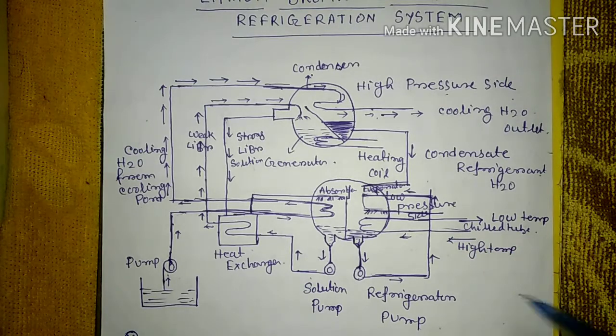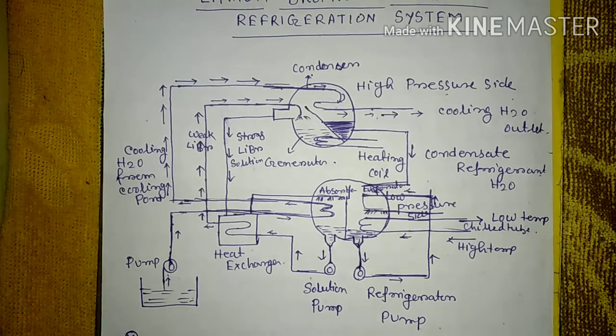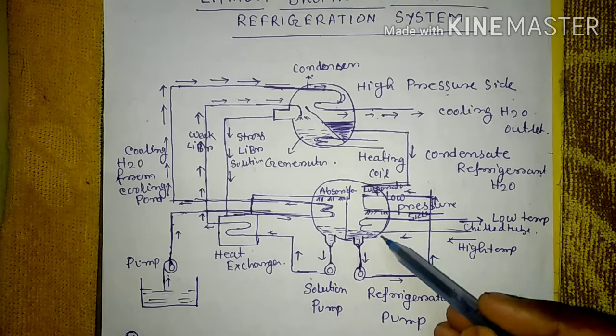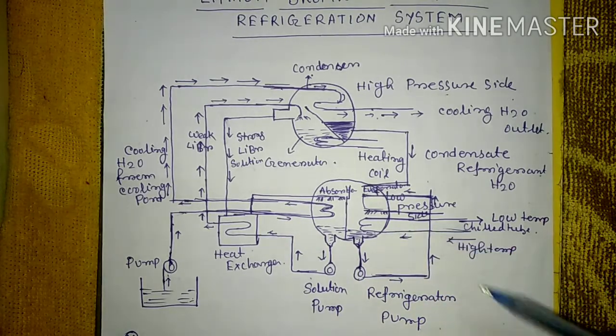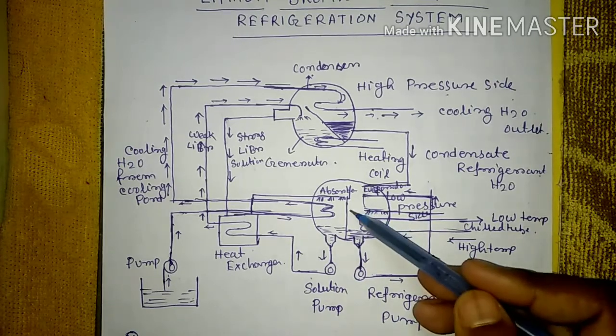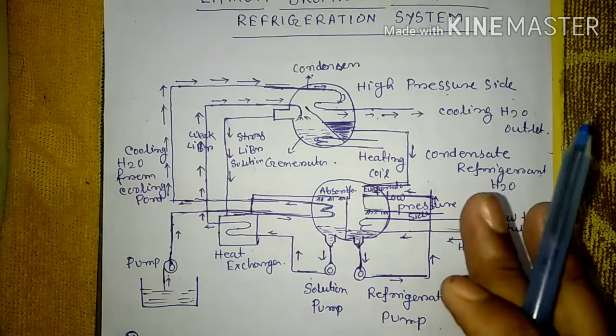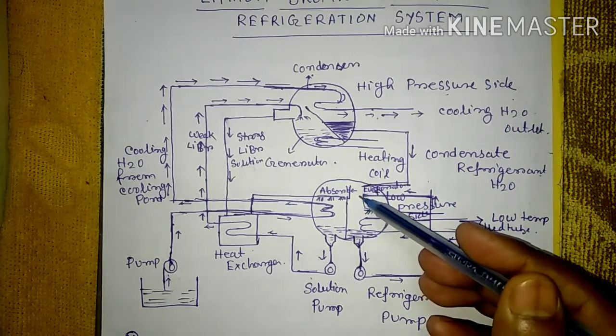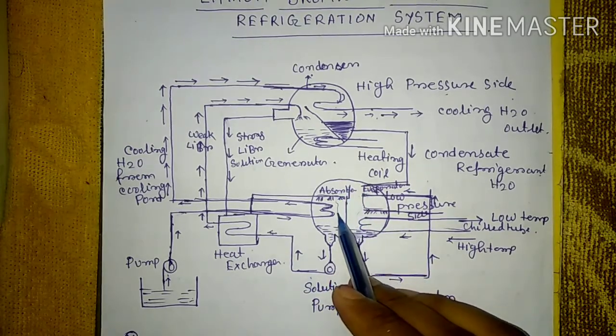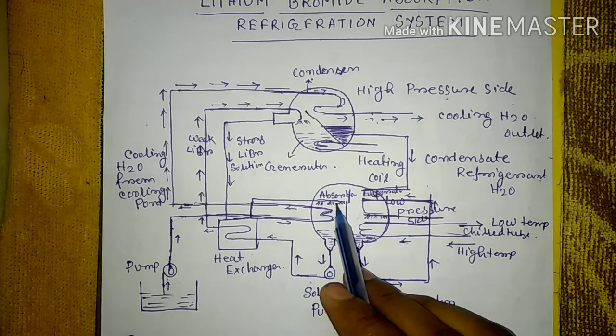When the sprayed water contacts the high-temperature chilled water tube, it evaporates, forming water vapor. Since the evaporator and absorber are on the low pressure side, this water vapor travels through the channel into the absorber, where it mixes with the lithium bromide solution.